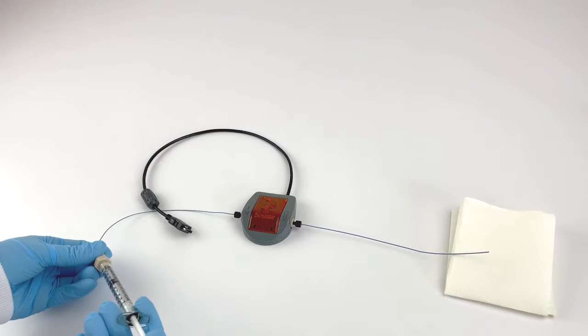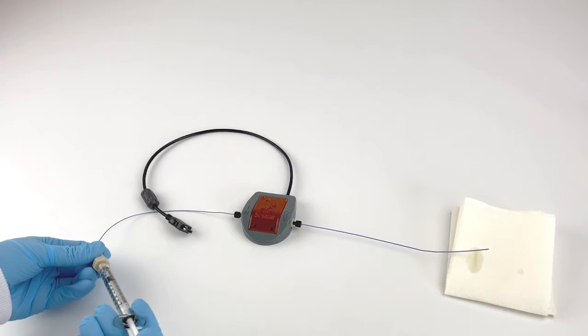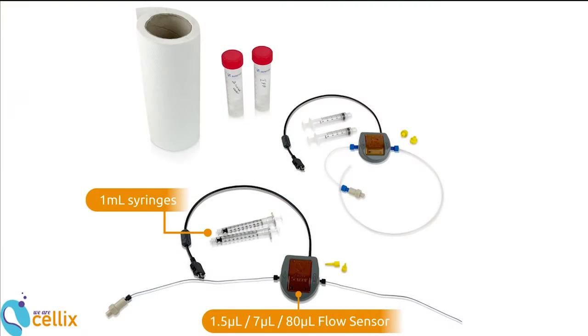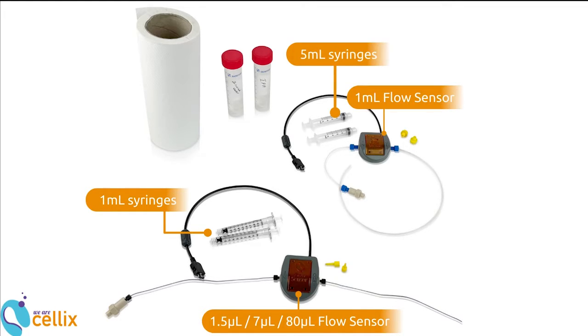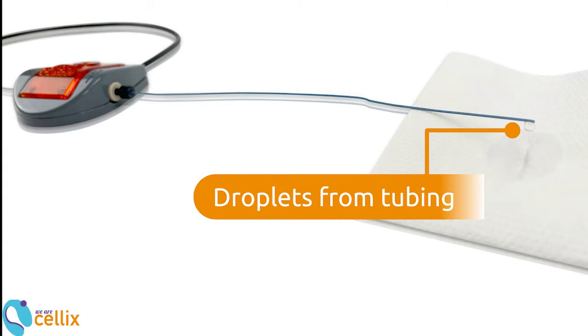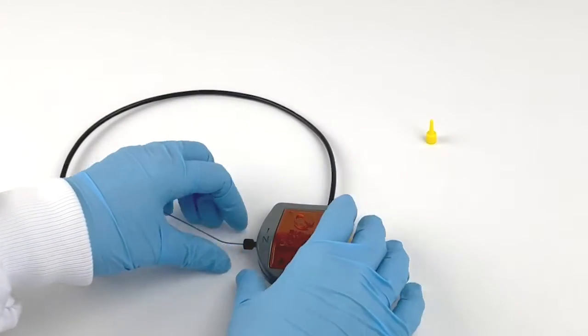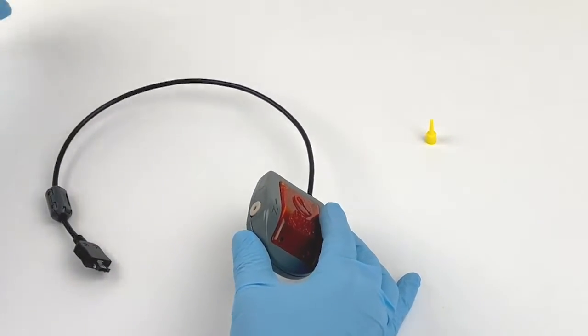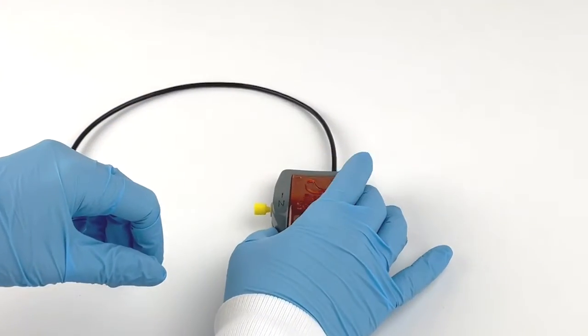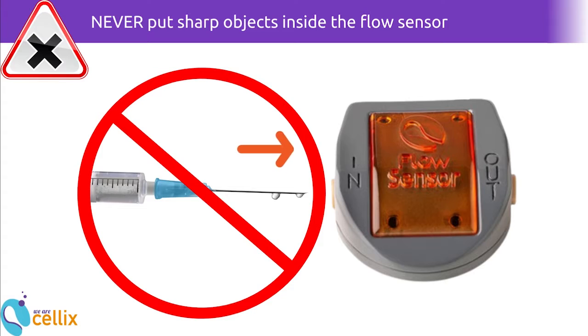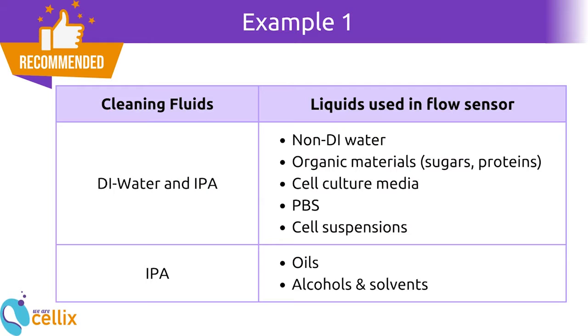Before storing the flow sensor, always drain the fluid. This is done easily by connecting an empty syringe and pushing air through the flow sensor. We recommend a 1 ml syringe for 1.5, 7 and 80 microliter per minute flow sensors, and a 5 ml syringe for 1 ml per minute flow sensors. Once there are no liquid droplets emerging from the tubing, it may be disconnected and the plugs provided should be installed on the fluidic ports for storage. Finally, never try to clean the flow sensor by mechanical means and never put any rigid or sharp objects inside the flow sensor.